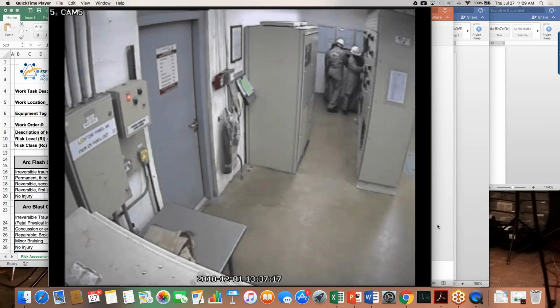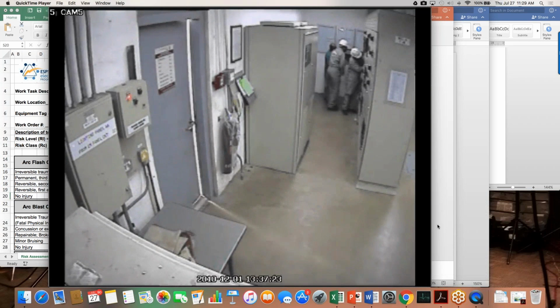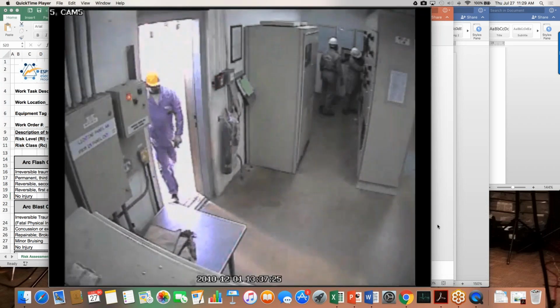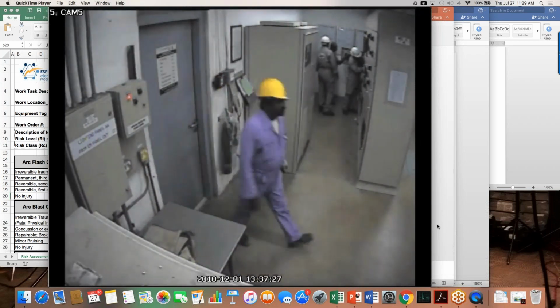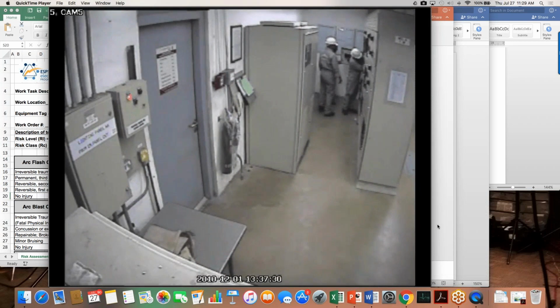Meanwhile, we have two other workers with a door to the MCC open beside him, obviously planning another job. They're confining him. They're distracting him. The worker's human performance behavior is deficient and becoming more deficient every second. He may be highly qualified and competent, but his human performance is impacted. He's going to make a mistake. An arcing fault ensues. This is a less than 8 calories per centimeter squared arc flash incident energy.